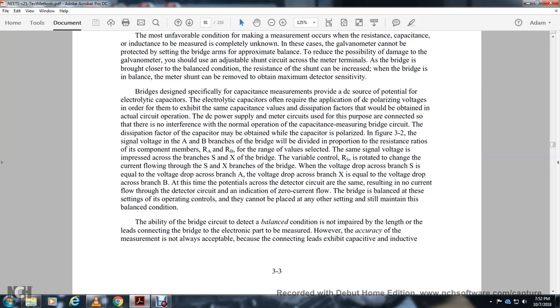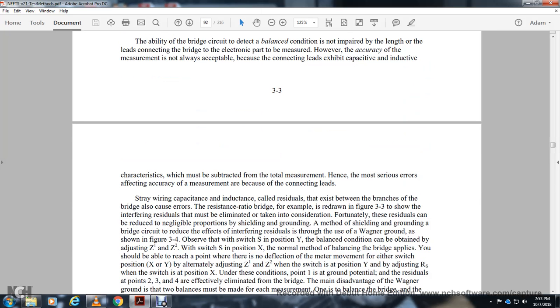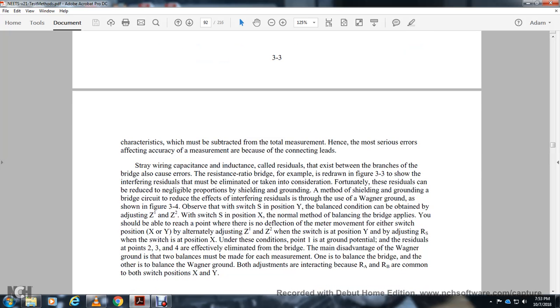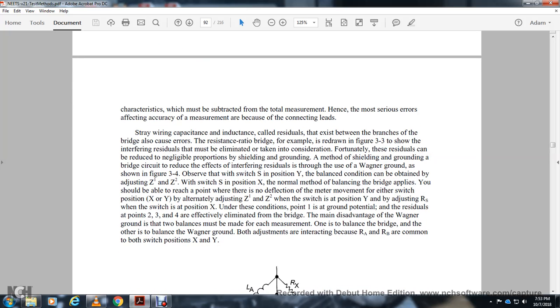The ability of a bridge circuit to detect the balance condition is not impaired by the length of leads connecting the bridge to the component being measured. However, measurement accuracy is affected because connecting leads have capacitive and inductive characteristics which must be subtracted from the total measurement. Residual errors exist between bridge branches — including stray capacitance and inductance — called residuals. Figure 3-3 shows that these residuals must be taken into consideration.